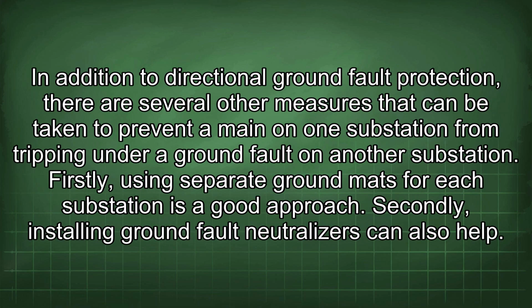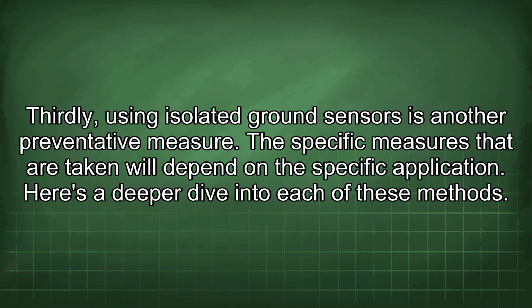In addition to directional ground fault protection, there are several other measures that can be taken to prevent a main on one substation from tripping under a ground fault on another substation. Firstly, using separate ground mats for each substation is a good approach. Secondly, installing ground fault neutralizers can also help. Thirdly, using isolated ground sensors is another preventative measure. The specific measures that are taken will depend on the specific application. Here's a deeper dive into each of these methods.